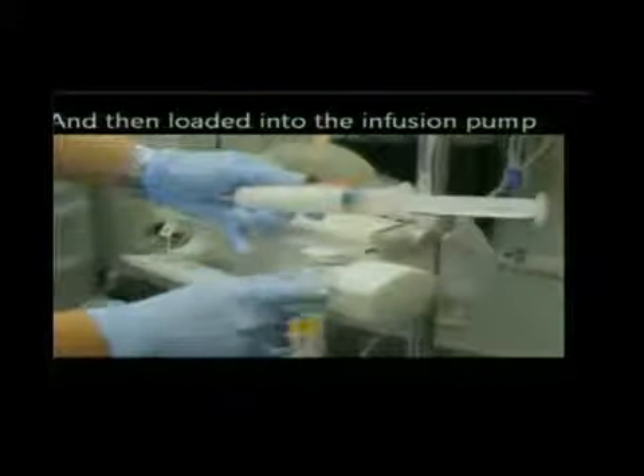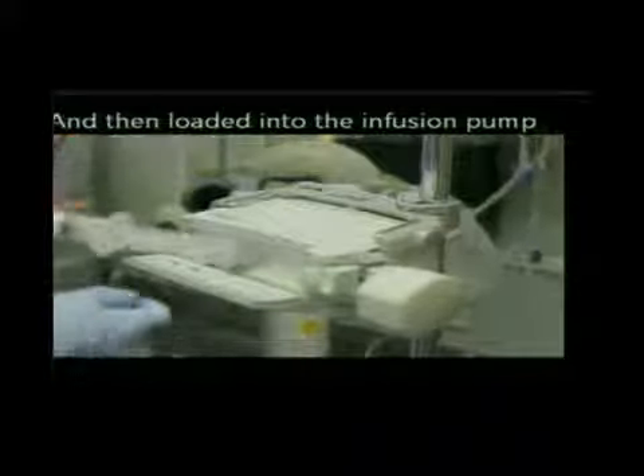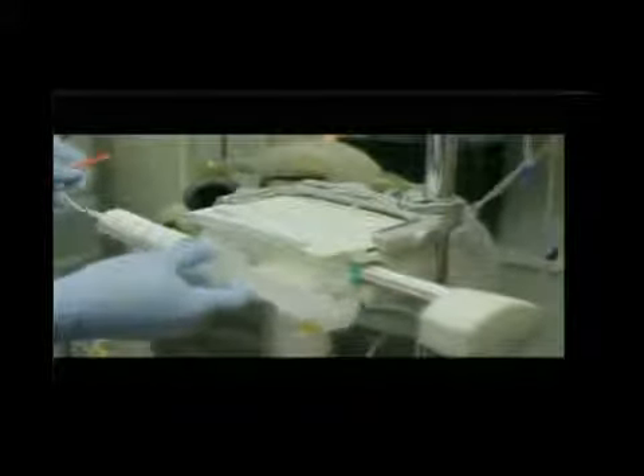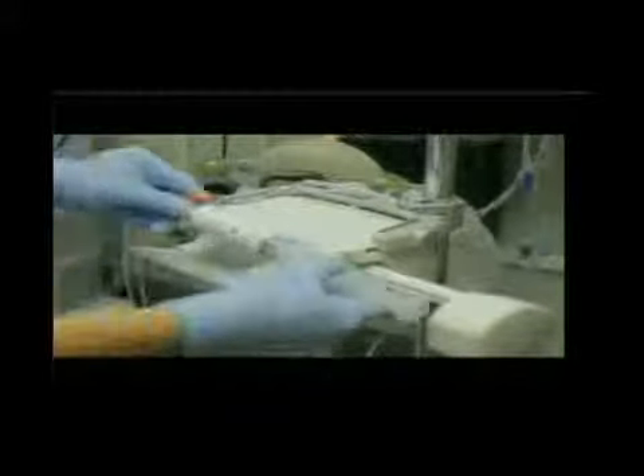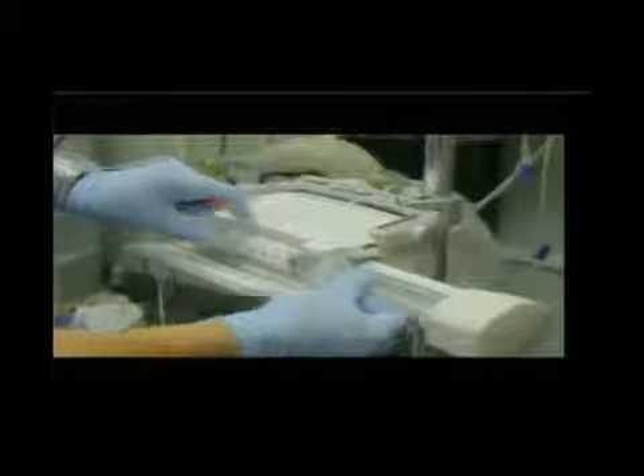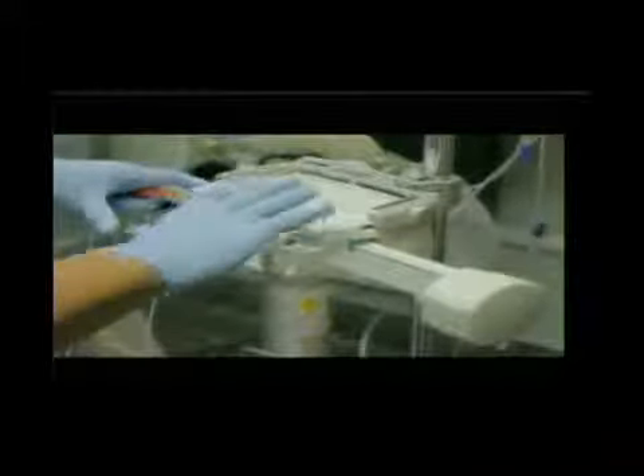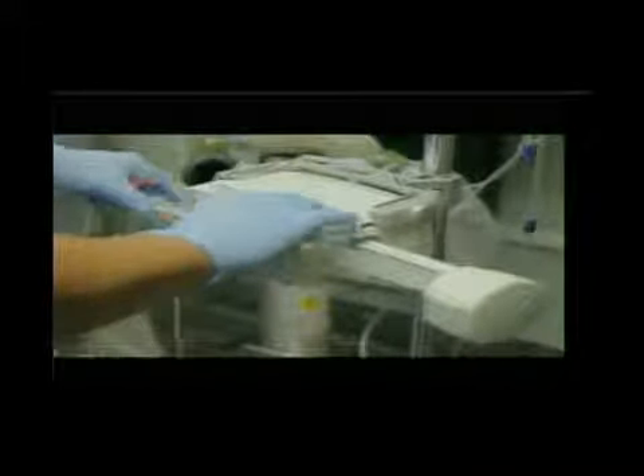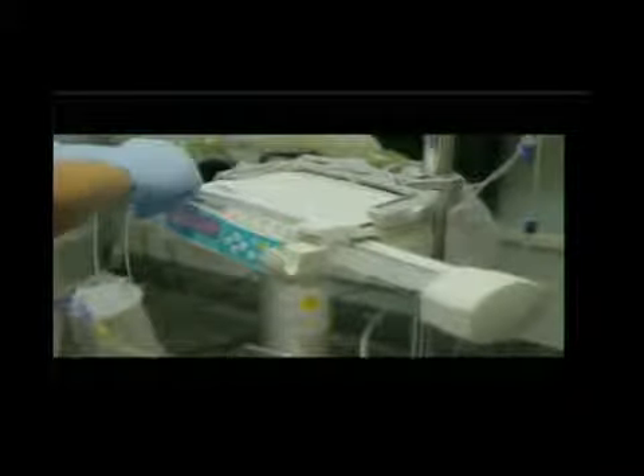Now he has the syringe, he has the tubing, now he has to put it into the pump itself, and then load it into the infusion pump, if you may continue. So this is a syringe pump. As you see the pump, that piece that's moving back is what is going to push the syringe forward in just a few moments. The syringe is placed into the pump. It is locked into place, shown here so that it can't move. And then the tubing is brought forward.